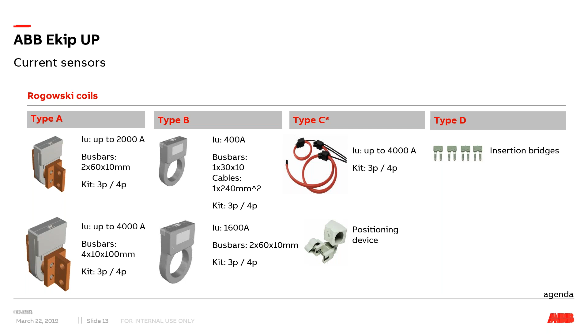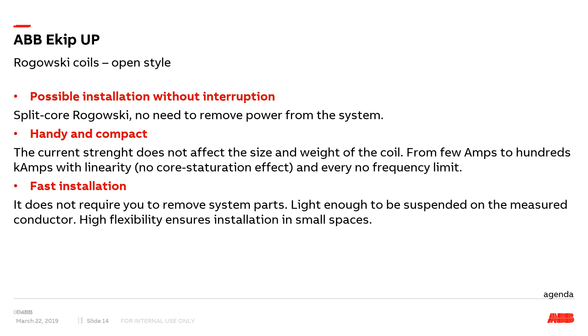So the open style is quite easy to install in either existing or new design, and the weight is quite light. What you need to be careful about in installing this open CT, open current sensor Rogowski style, is that you need to be wary of the direction of the current to get the right reading. And essentially it's light enough to be suspended on the measured conductor as well. And it's insulated too with the actual material that it has been designed with.